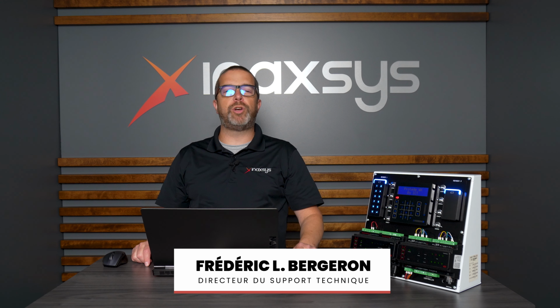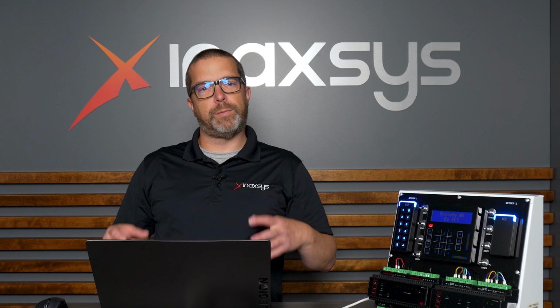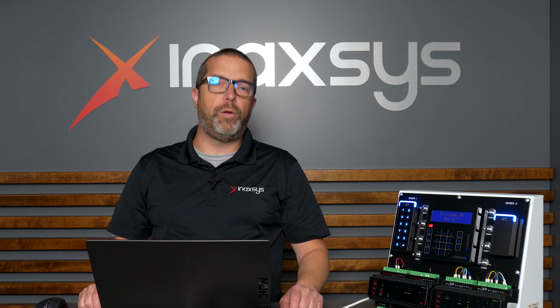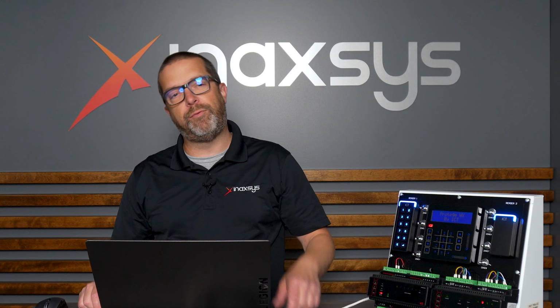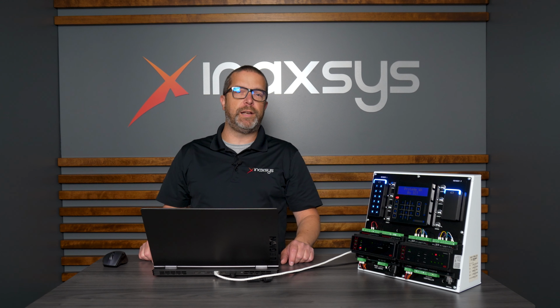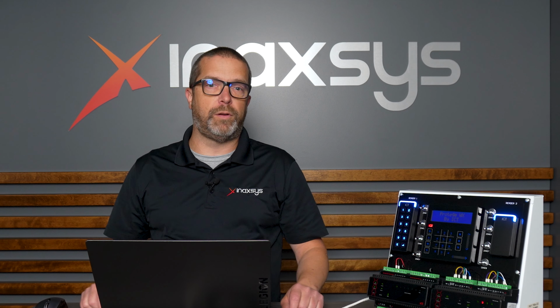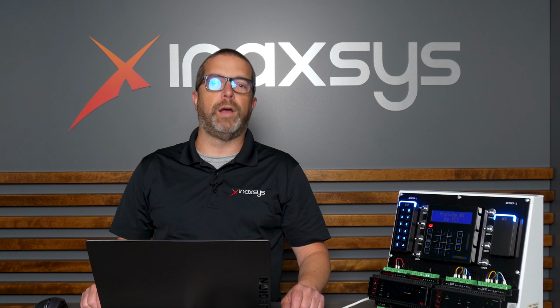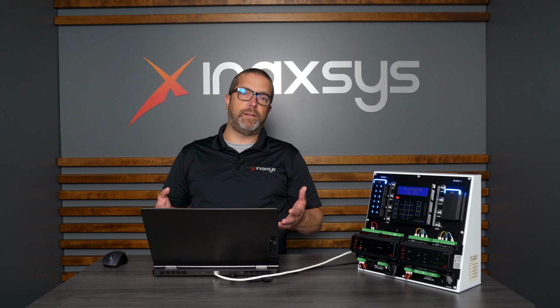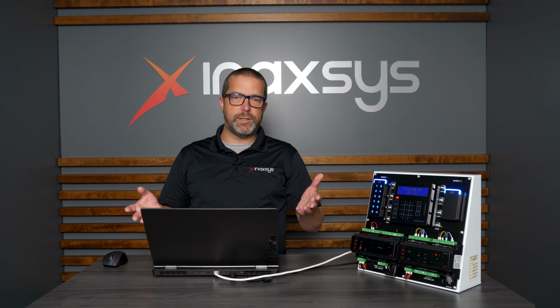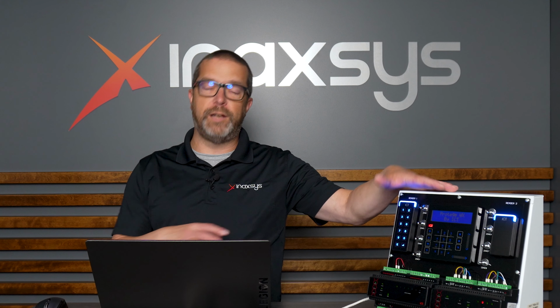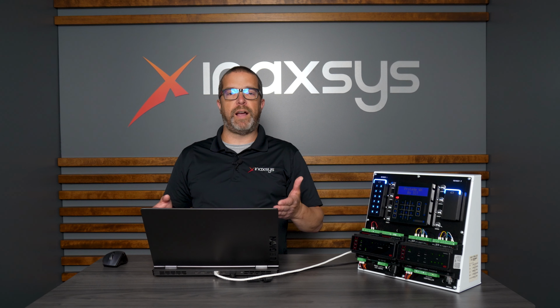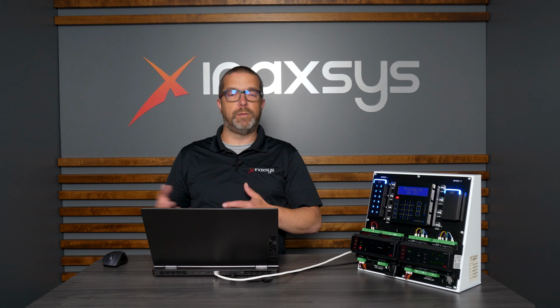In this video, I want to show you how to configure some zones and the system to only report alarms after hours. We've had this question from a couple of customers lately, so I decided to make this tutorial so we can help you understand how this is done. The idea is I'm going to create a schedule for, let's say, work hours. During the day, if there are alarms, it's going to be just a local alarm on site. After hours, when the schedule becomes invalid, the system will switch to a secondary input type so that alarms are sent to the monitoring station.